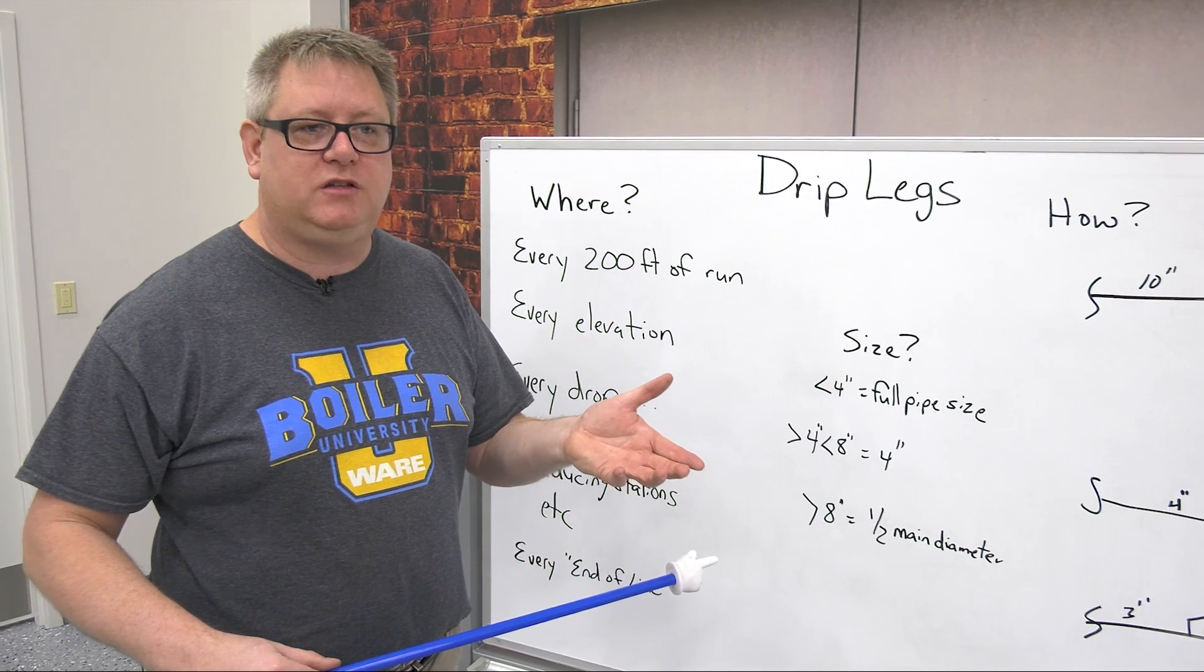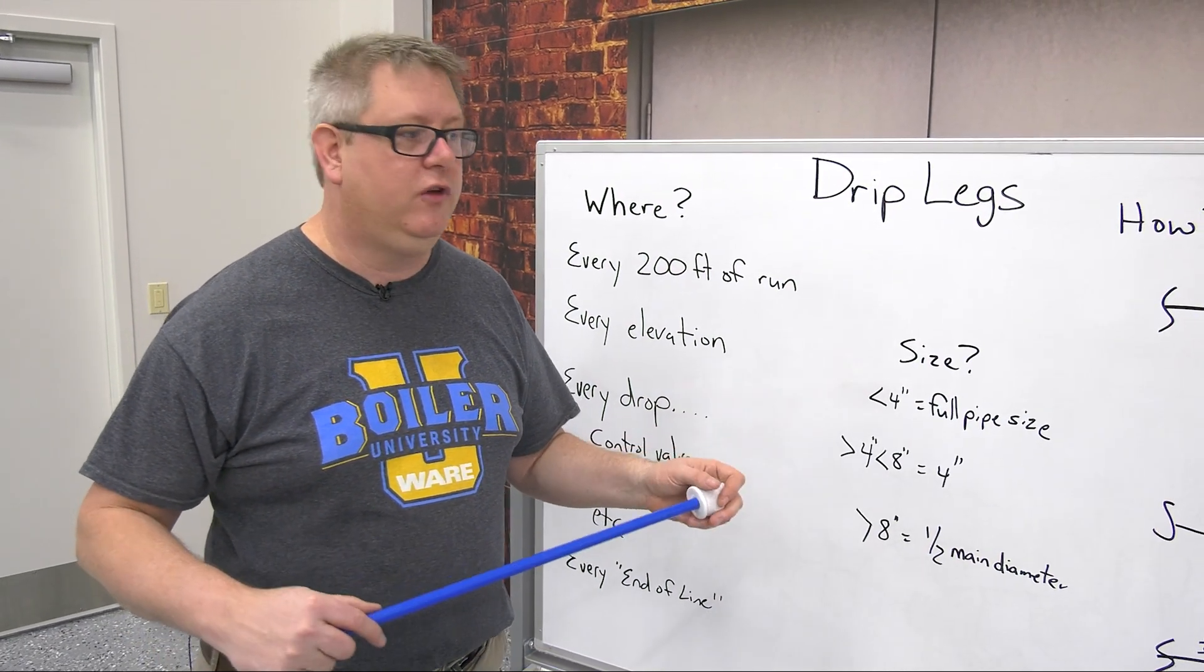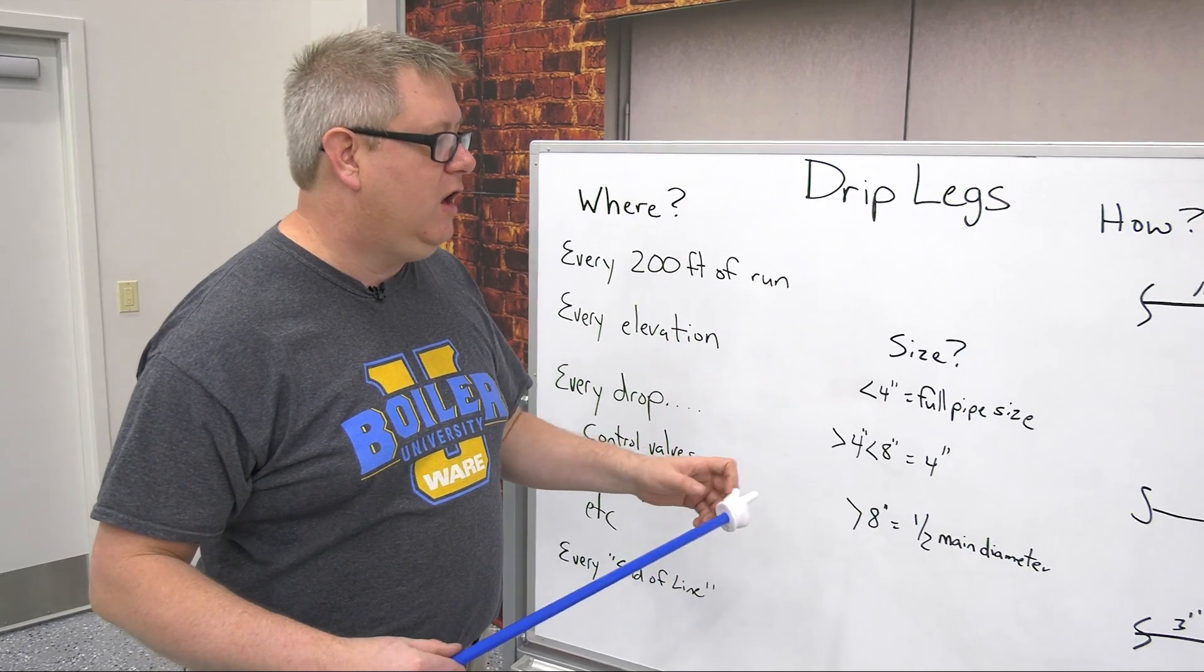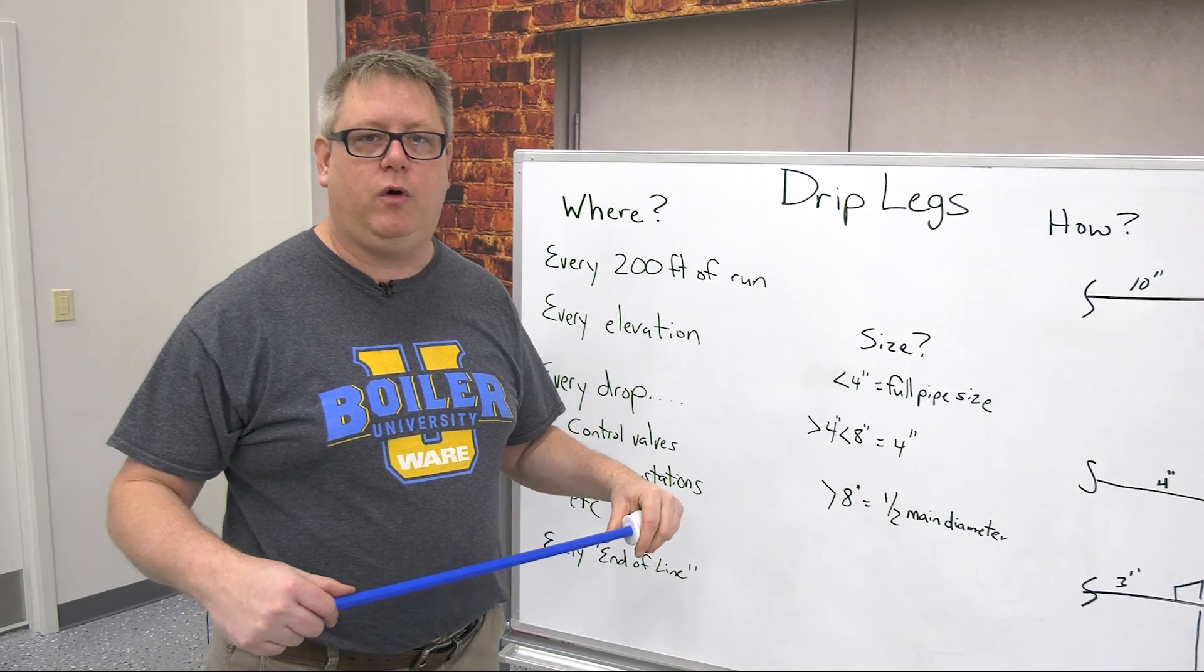Really the cost in piping is the labor. So if we go ahead and make those drip legs full size or as large as practical, then we're going to get good condensate removal at those points.